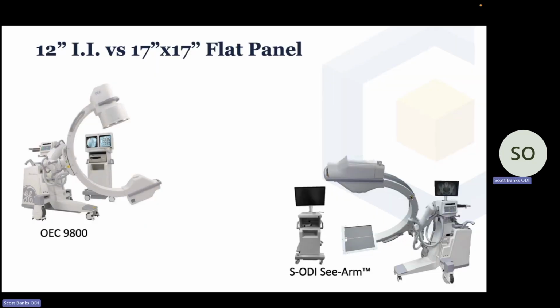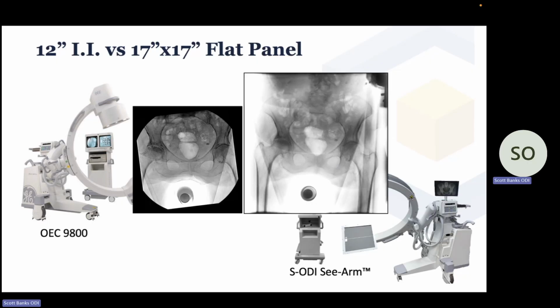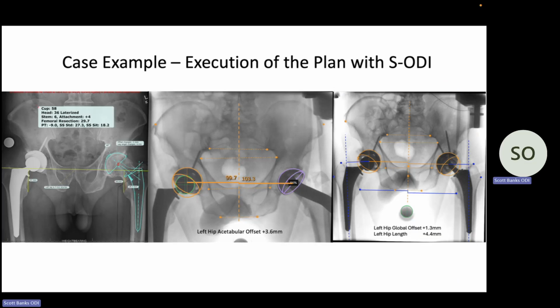So what we set out to do as our first effort within orthopedic-driven imaging was to go from the typical 12-inch image intensifier to a 17 by 17-inch flat panel detector. As you see here, the difference is profound. With the 17 by 17-inch image, you get wonderful image quality, but you also get twice the imaging area that allows you to see the entire pelvis, as well as about the proximal half of the femurs bilaterally. And with all that anatomy in view, it's possible to get much better aligned images and to perform more accurate measurements. So here's an example, all done within the OR using the surgical ODI or SODI unit.